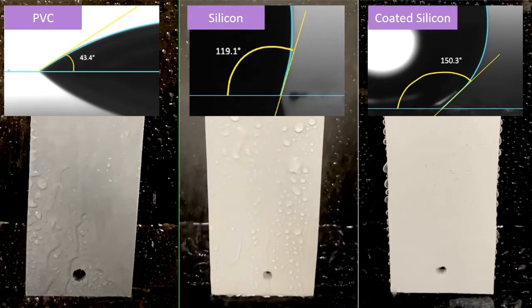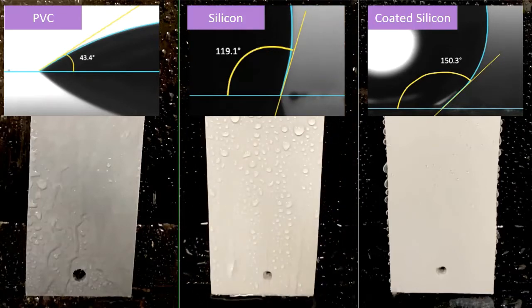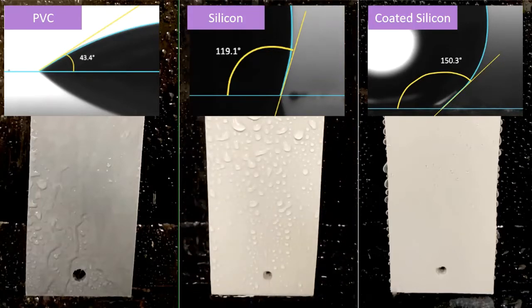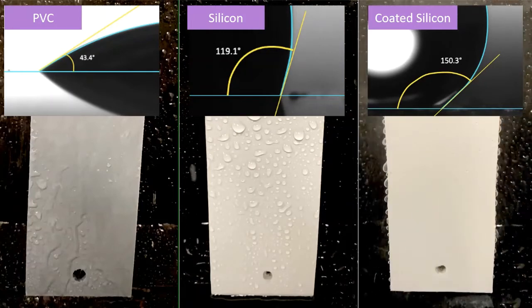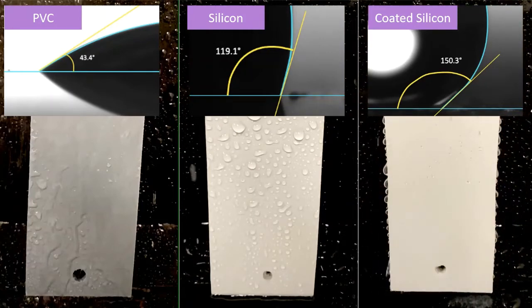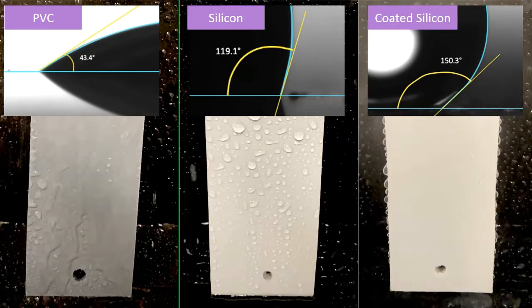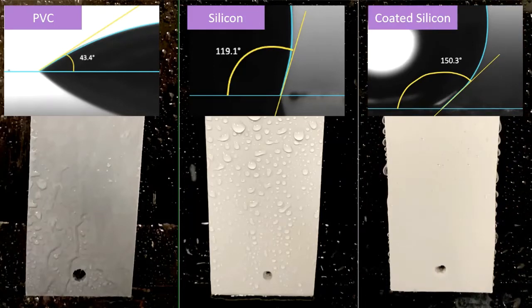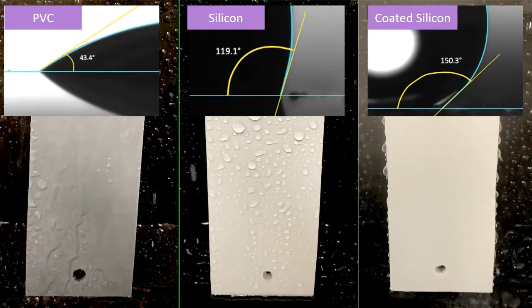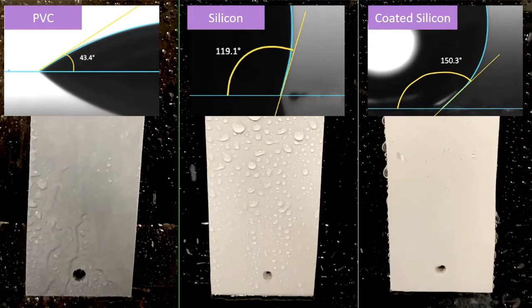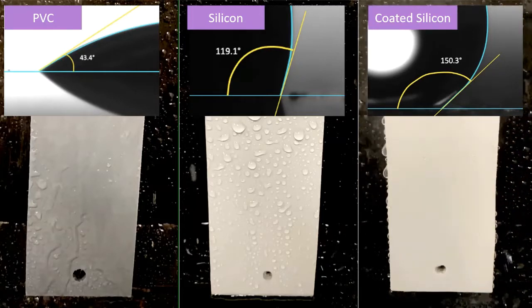Despite the benefits of hydrophobicity, silicone insulators still suffer from the inevitable surface aging mechanisms, which decrease their ability to perform over time. A potential method to combat this is to apply a superhydrophobic coating, which increases the contact angle beyond 150 degrees, thus delaying the formation of conductive paths for longer than a hydrophobic surface. Such use presents an engineering challenge, as currently no standard exists for the assessment of hydrophobic coatings. In addition, due to their size and placement, applying coatings to live insulators requires careful risk assessments.